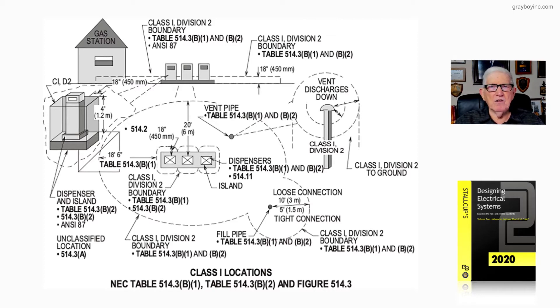Notice at the very top of the illustration, we're going to look at a Class 1 Division 2 boundary in accordance with our Table 514.3B1 and B2. Now the ANSI-87 you see there deals with inside the pump, and where there's no barrier is Class 1 Division 1 inside.